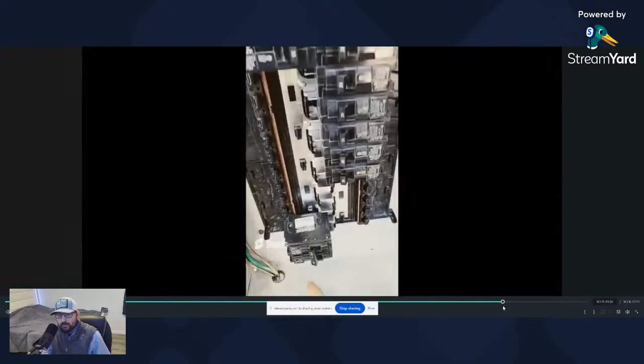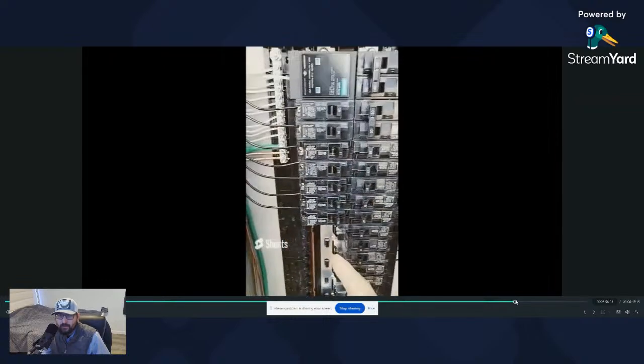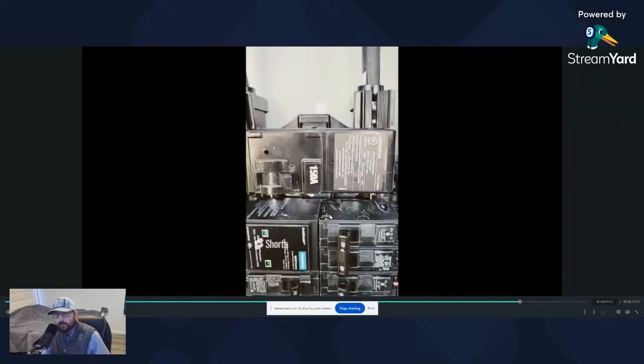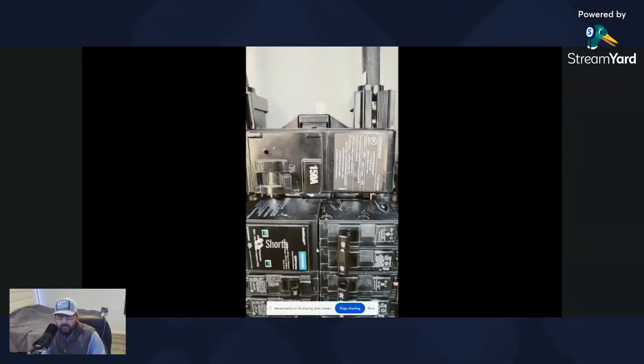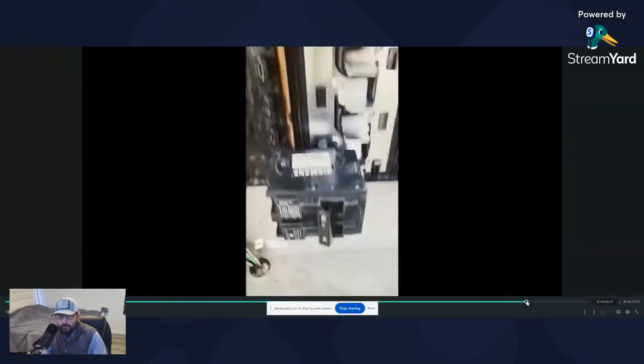That's it. Okay, so in this case, they do have a 40 here. The bus is rated at, actually, I cannot read that. I actually can't read it, but I think it's a 200 amp bus. This is where you'd see your bus ratings. And you're going to see they installed a 150. So we can install that much of a bigger breaker. You would take 240 minus 150, and therefore you can be larger than a 40 amp breaker on the back fed.